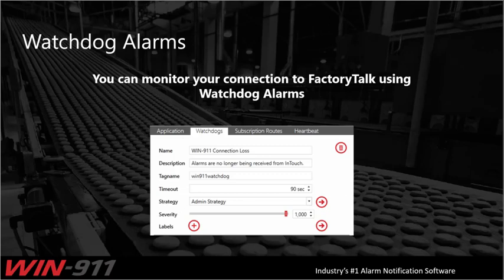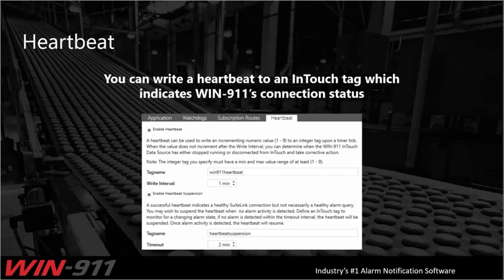You can notify specific people or even set up a do-not-notify strategy if it's becoming something that happens more often than it should. That brings us to the heartbeat as well. You can write a heartbeat to an InTouch tag which indicates connection status — we're talking to SuiteLink, SuiteLink is talking to InTouch and writing a value to a tag you've created, basically indicating its operational status, its vital sign — the heartbeat.